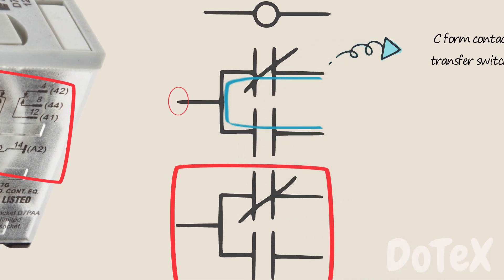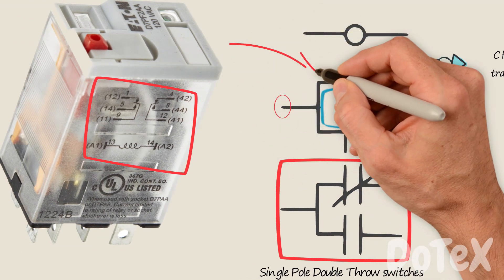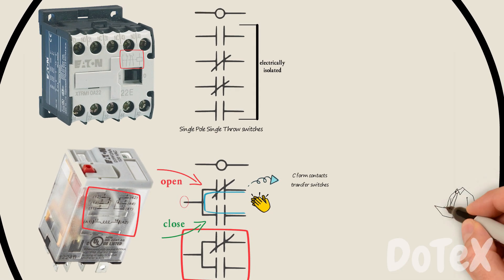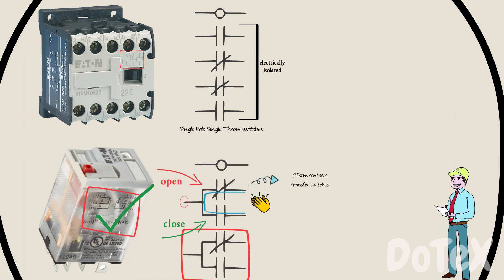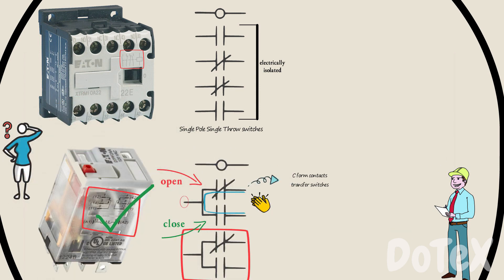Can you see why they are called C form contacts? Perfect. When one side is open, the other side is closed and vice versa. Manufacturers sometimes use a single pole double throw switch symbol to make the transfer function very clear to the user.